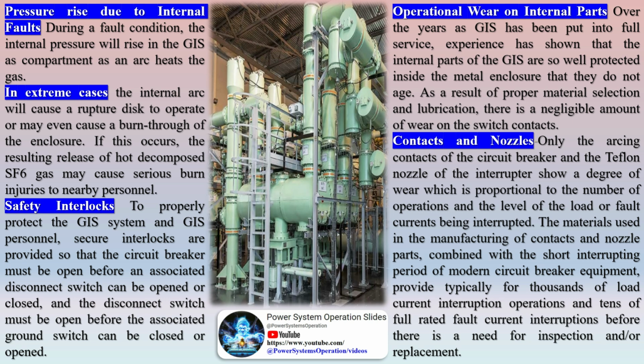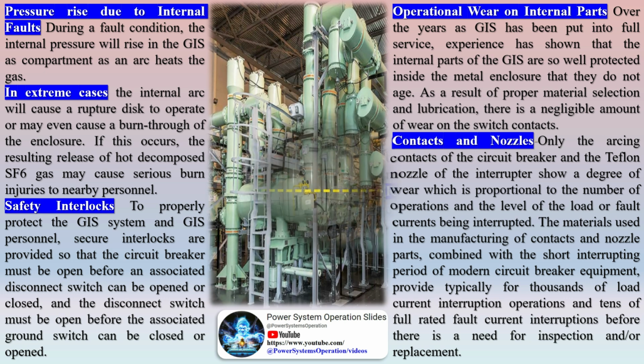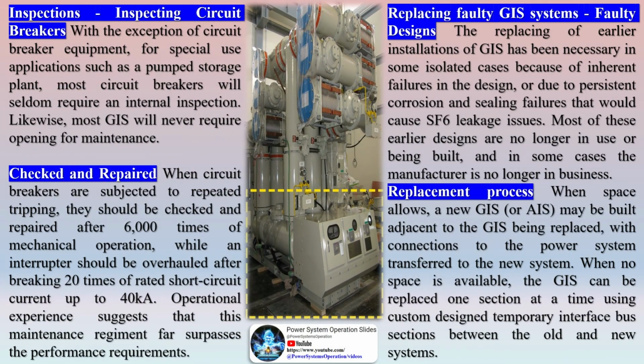To properly protect the GIS system and GIS personnel, secure interlocks are provided so that the circuit breaker must be opened before an associated disconnect switch can be opened or closed, and the disconnect switch must be opened before the associated ground switch can be closed or opened.